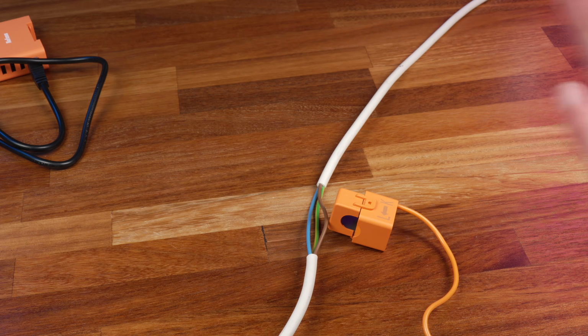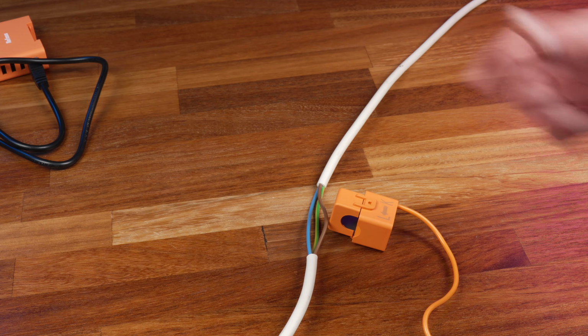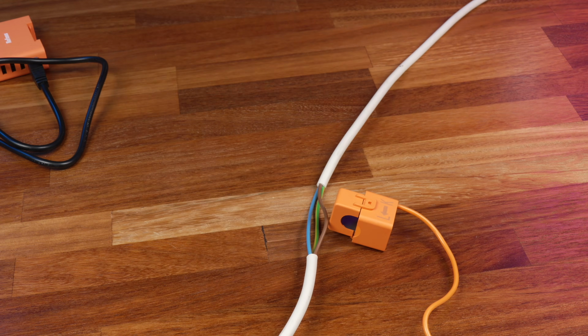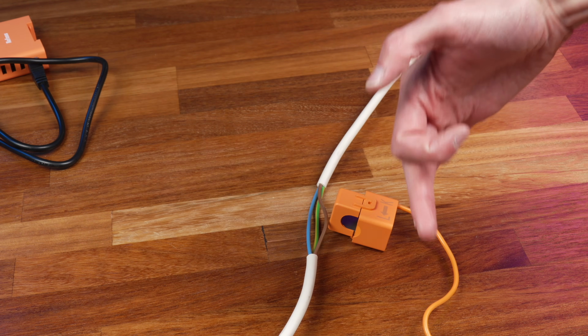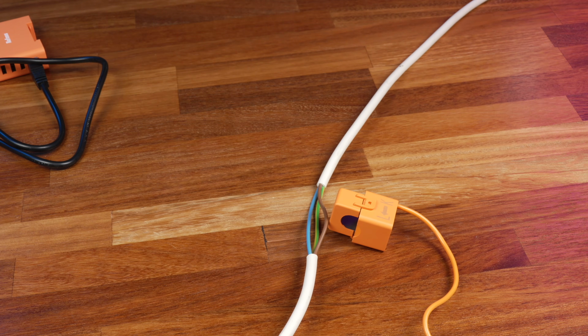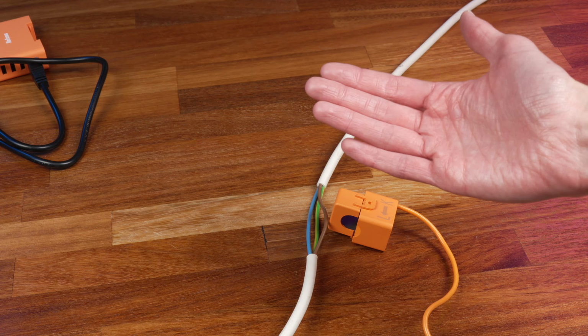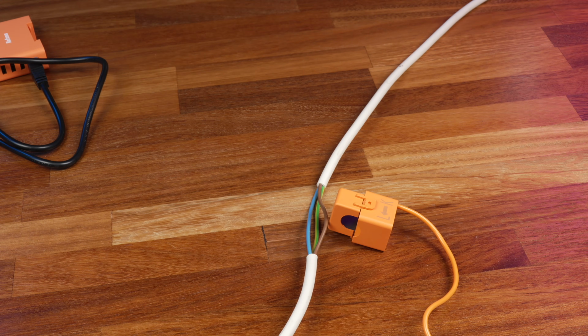The only time this might be a bit different is where I want to put a CT on the circuit that's connected to my solar inverter. If I install the CT with the arrow pointing in the direction of current flow, which would be away from the inverter and towards the rest of the circuits, the readings will be tracked as consumption rather than production. So with that, it may be preferable to treat it like any other circuit and point the arrow towards the inverter. So that any generated power gets tracked as production, and power consumed by the inverter when it's not generating, or potentially charging batteries if you have battery storage, will get tracked as consumption.